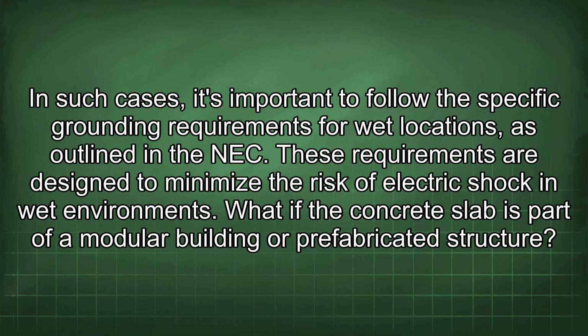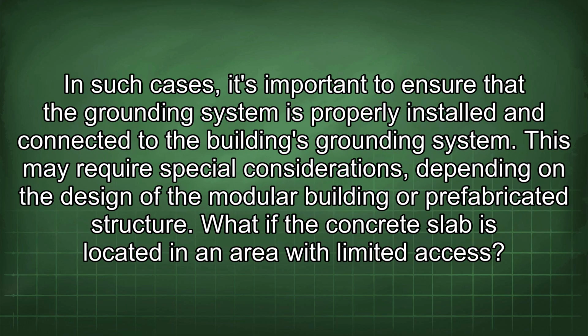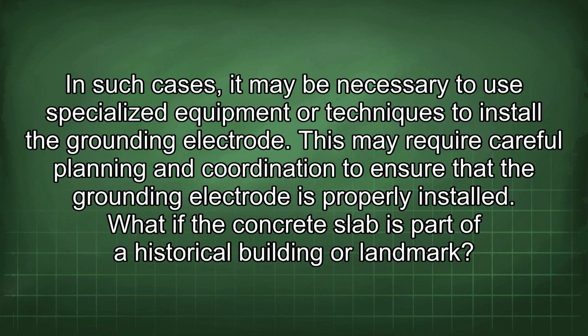What if the concrete slab is part of a modular building or prefabricated structure? In such cases, it's important to ensure that the grounding system is properly installed and connected to the building's grounding system. This may require special considerations, depending on the design of the modular building or prefabricated structure. What if the concrete slab is located in an area with limited access? In such cases, it may be necessary to use specialized equipment or techniques to install the grounding electrode. This may require careful planning and coordination to ensure that the grounding electrode is properly installed.